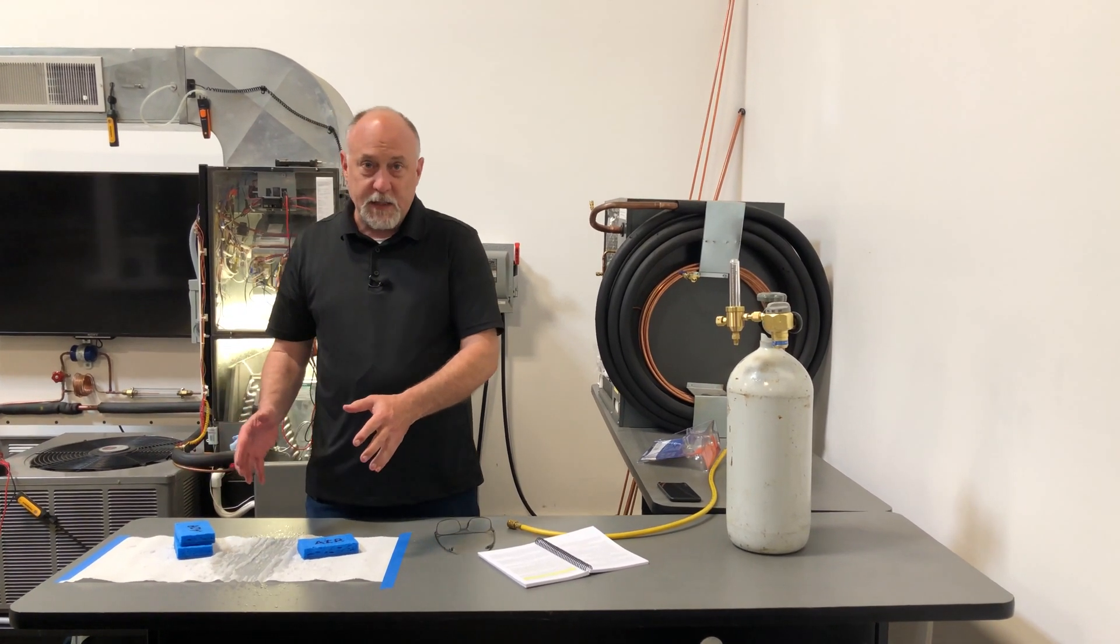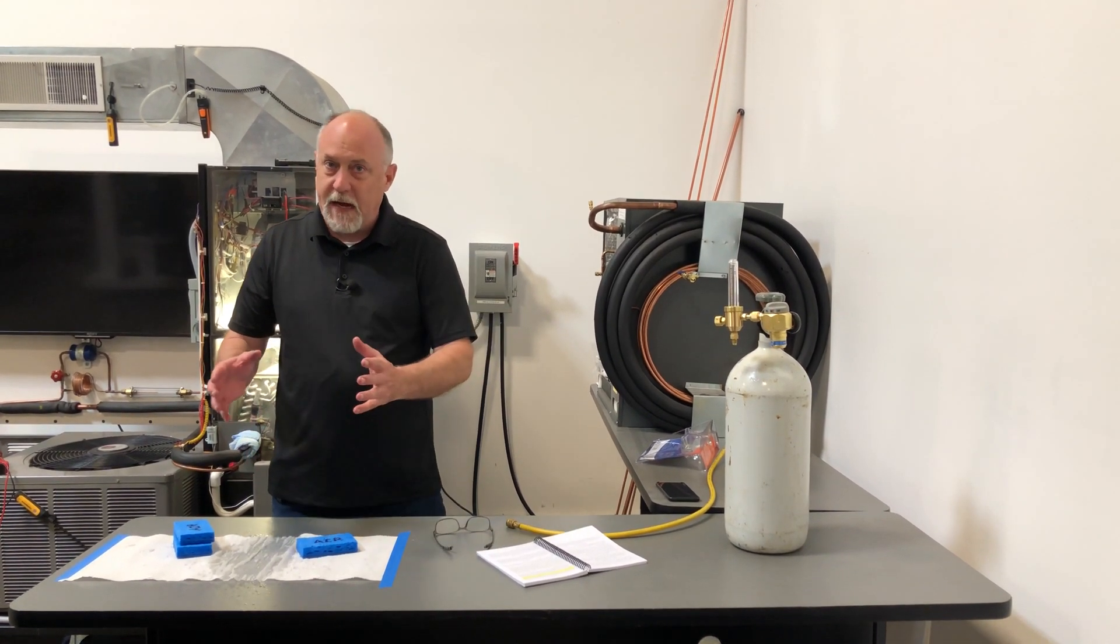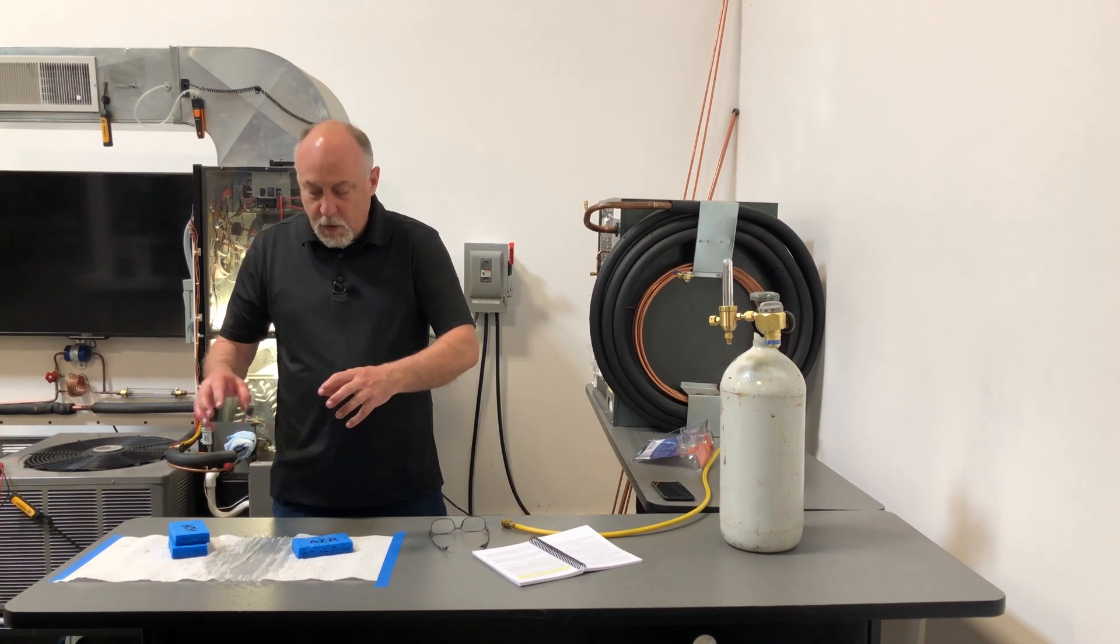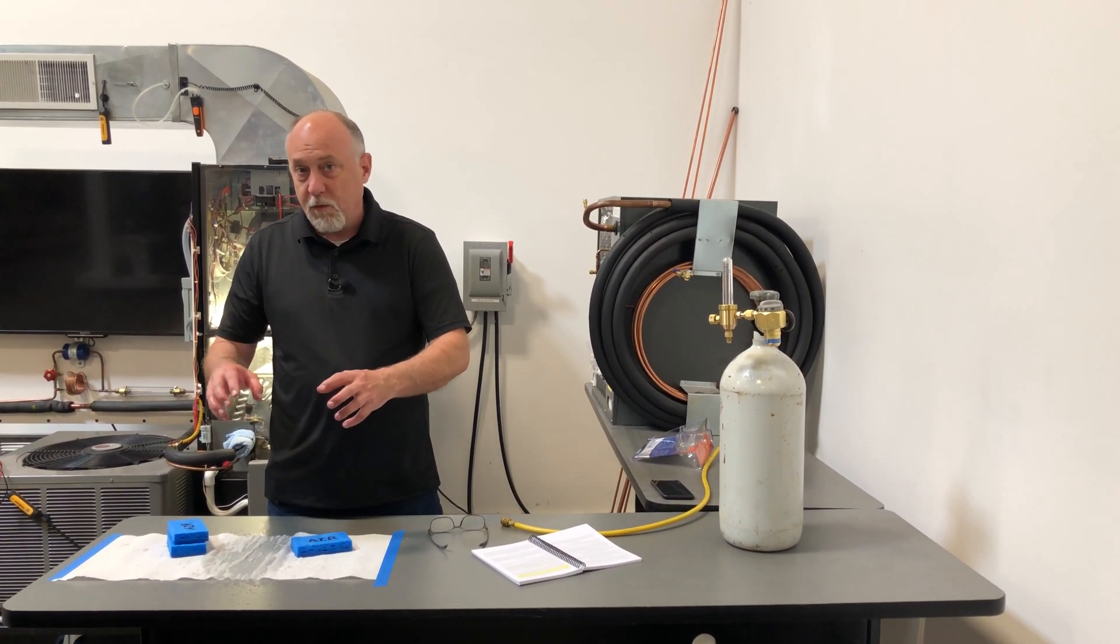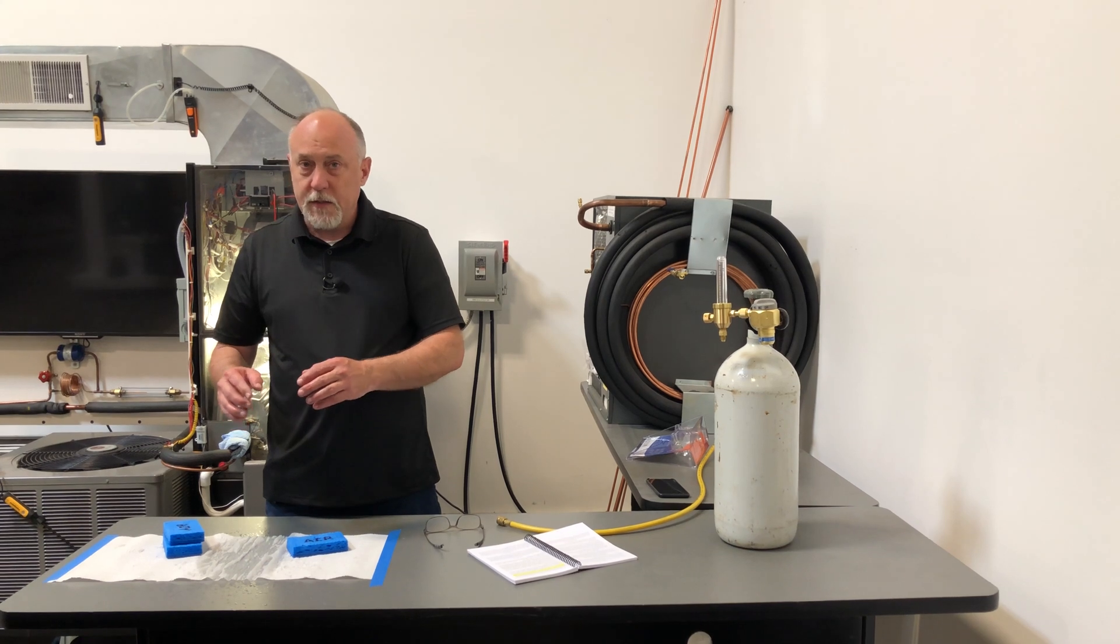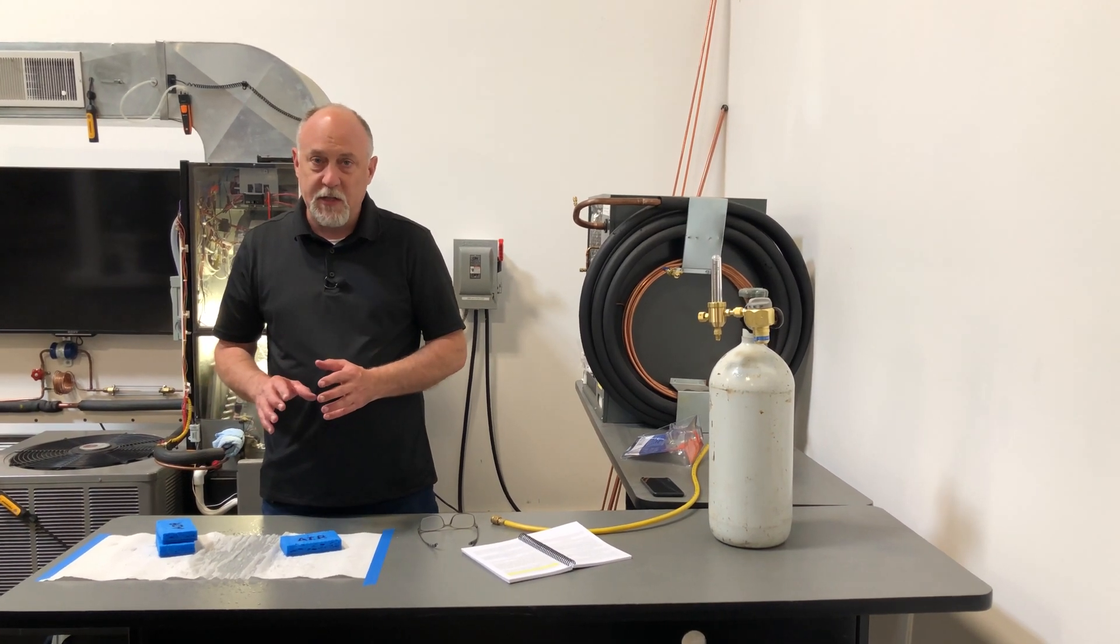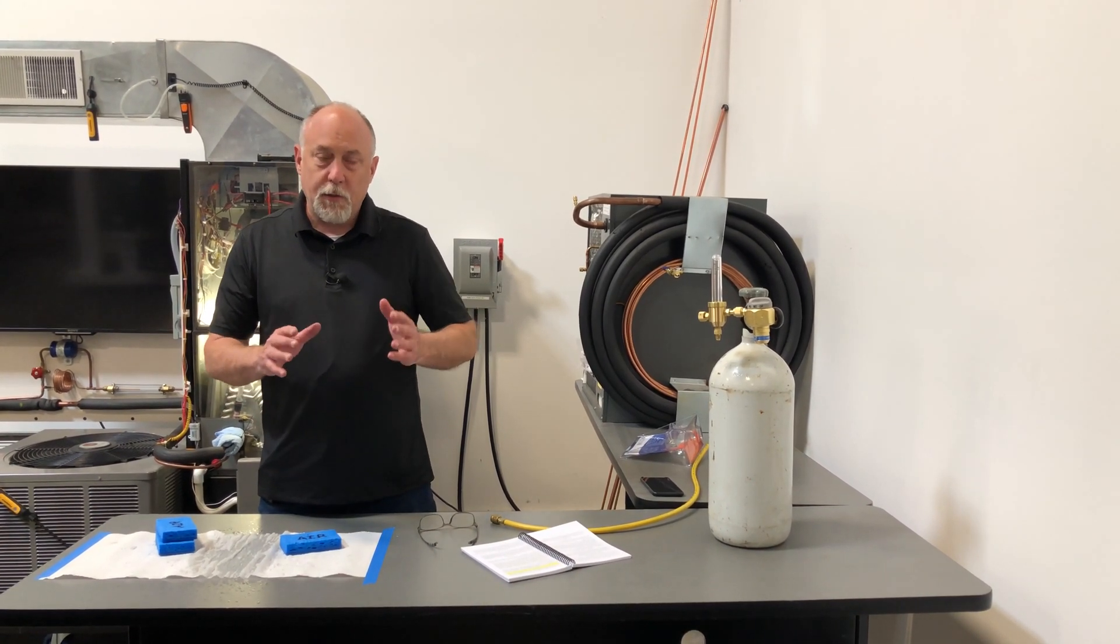Now just imagine how long this paper towel is going to take to dry out. Remember there's no flow in a vacuum, we're just reducing pressure, so all this moisture has to boil away before we can carry it out of the system. If you want to decrease your evacuation time substantially, the secret is purge with nitrogen.